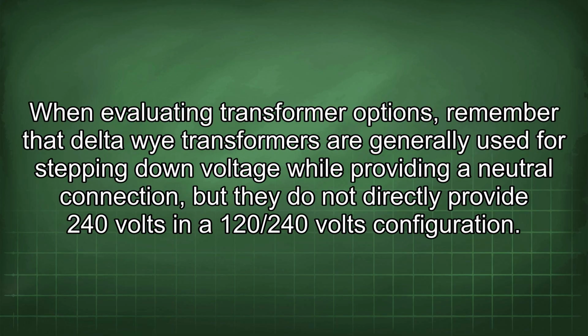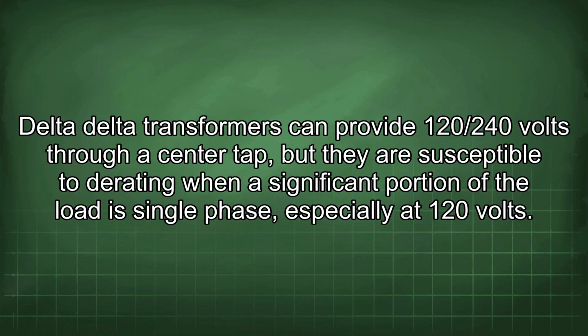When evaluating transformer options, remember that delta-Y transformers are generally used for stepping down voltage while providing a neutral connection, but they do not directly provide 240 volts in the 120/240 volt configuration. Delta-delta transformers can provide 120/240 volts through a center tap, but they are susceptible to derating when a significant portion of the load is single-phase, especially at 120 volts.